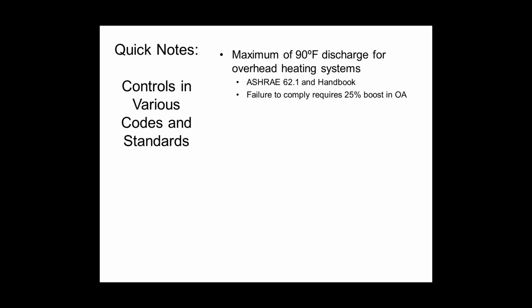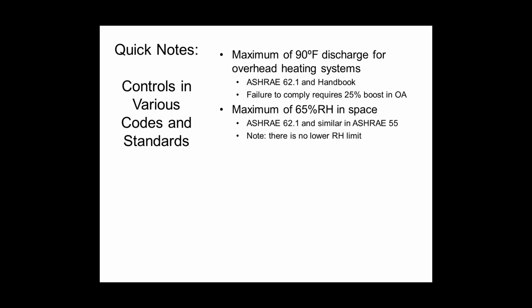But the ceiling is going to be 102 and the floor is going to be 51, and people are going to be upset. So the cooler discharge air actually lets the diffusers do their job, which is to mix the air and throw it into the space. That means I get more uniform temperature between ceiling and floor, which means fewer people are upset, and I don't have to take a penalty on the outside air requirement. So keep the discharge air below 90, or probably below 85. If you're only heating the space to 70 degrees, your maximum discharge air would be 85.